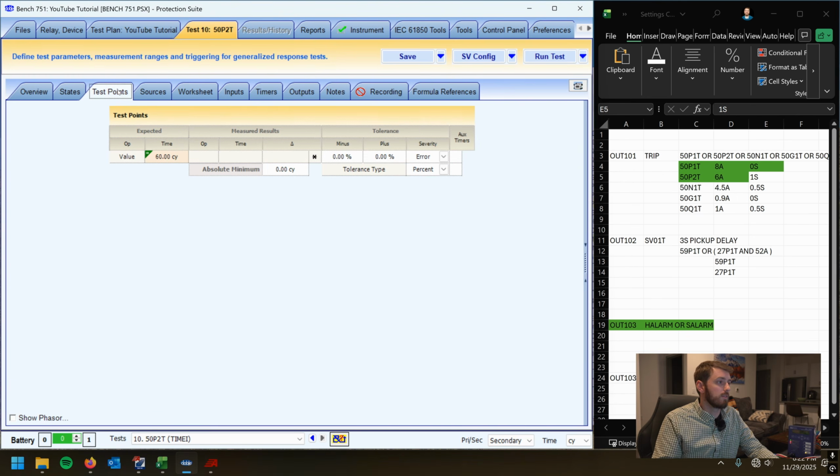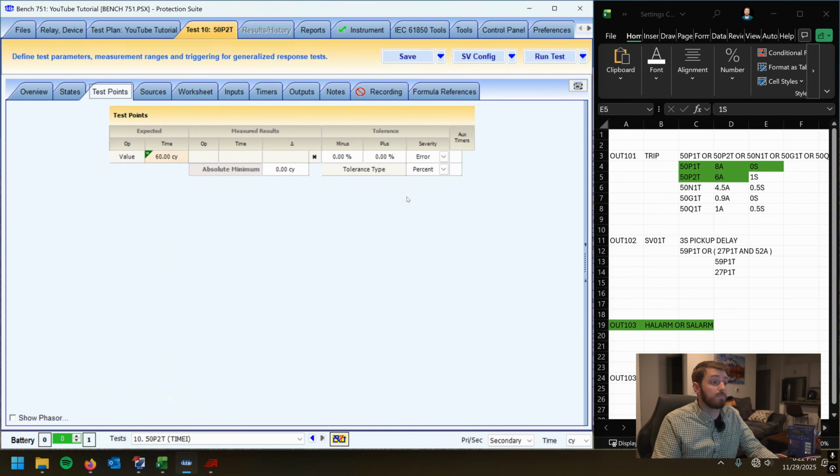It's really not going to take that long for this test. Our tolerance here per the book is 0.5%. So we're going to go plus minus 0.5%. We're going to run this, and it might pass. We'll talk about it if it doesn't. The issue that I'm expecting will certainly come up in this episode.